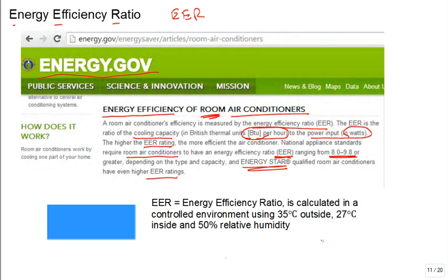When you're running an air conditioning system, wouldn't it depend on how hot the outside is and how humid the outside is? Sure. So they basically specify this is your standard outside temperature and outside humidity. And then you try to run it with a standard 50% inside and 75 degree F inside temperature. So this is your inside temperature and relative humidity as well. So this looks a lot like our coefficient of performance, doesn't it? What was our definition of coefficient of performance for a refrigeration system? It was how much work to cool. So I like a large amount of cooling for the amount of work provided. And here they're just saying, oh, it's a rate of cooling and a rate of energy provided, and we have to plug it in and we consume electricity, so take it all the way back to the electricity, not just the shaft to run the compressor.